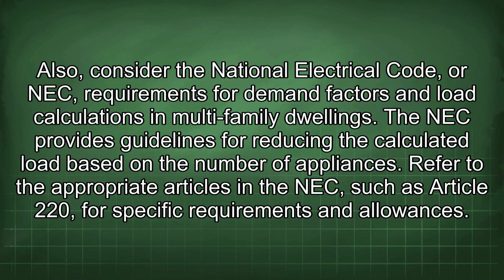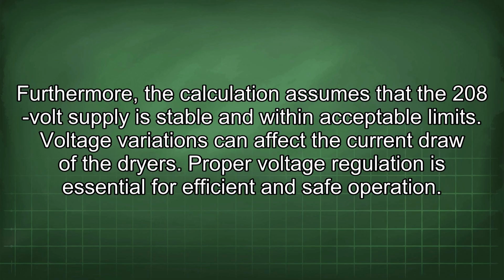Also, consider the National Electrical Code, or NEC, requirements for demand factors and load calculations in multi-family dwellings. The NEC provides guidelines for reducing the calculated load based on the number of appliances. Refer to the appropriate articles in the NEC, such as Article 220, for specific requirements and allowances. Furthermore, the calculation assumes that the 208 volt supply is stable and within acceptable limits. Voltage variations can affect the current draw of the dryers. Proper voltage regulation is essential for efficient and safe operation.